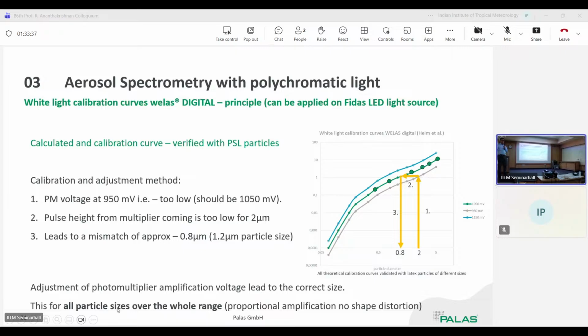So you see light scattering which is actually not existing, and this is next to 175 nanometers in that area. That's the lowest. For these light sources which we use, we have other, stronger light sources, then we go down to 120, but that's not necessary for emission measurement. So the PM voltage, if too low, should be 1050. This is the situation: the signal is too low. We increase the photomultiplier voltage and finally end up at a size which is correct to what we expected, and this over the whole range. That's our calibration feature, and you can do this easily on the device. You will see it later. You can test it by yourself. That means it's done, and it's exact.